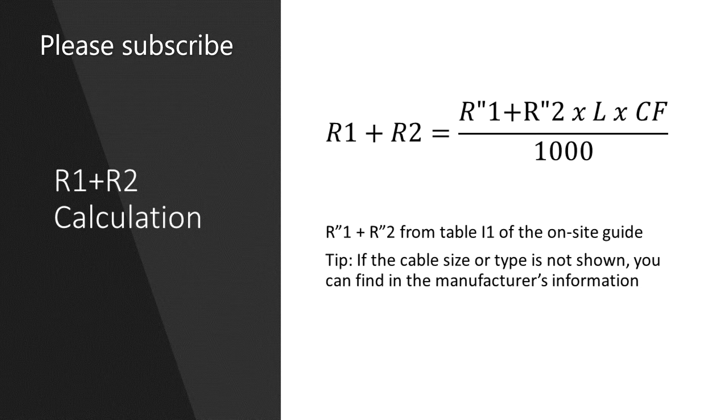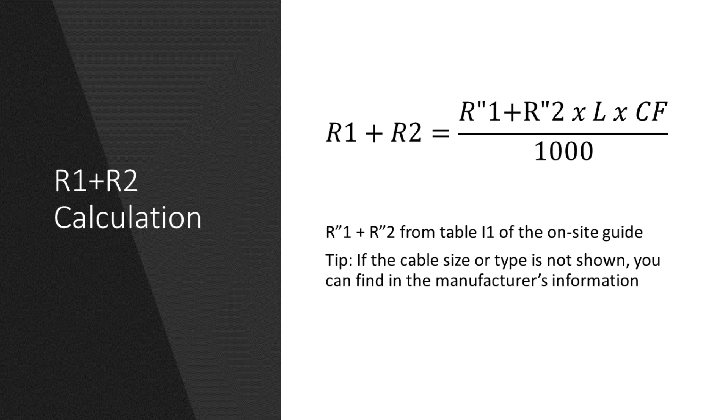So this is the formula for R1 plus R2. We take the tabulated values for R1 plus R2 in milli-ohms per meter from table I1 of the on-site guide, multiply by the length of the circuit and then multiply by a correction factor and then divide by 1000.